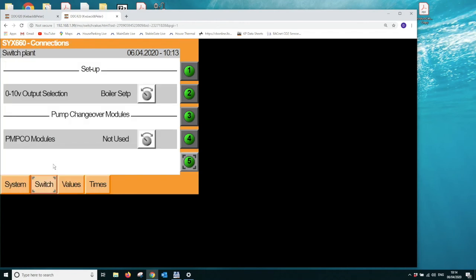Okay, so we're not going to be using the 0 to 10 volt output, so I'll just leave that set as VT valve. Pump changeover modules is the final option. If you're using our pump changeover modules where you've got 2 pump heads being changed over on fault or for flow failure, that module will coordinate what the lead pump is, and what we need to do is, given certain applications of the controller in certain times of the year, it may be that the pump output is always energized from the SYX controller. So for example, if it was a day-night setback operation, the pump would always be in operation, so we would have to forcibly turn the pump off for a short period of time in order for the pump changeover module to do its weekly rotation.